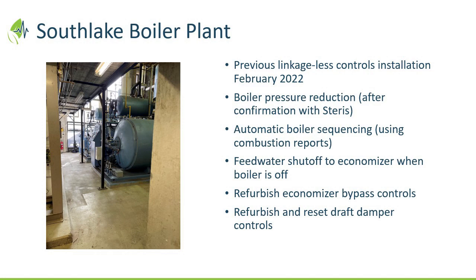My recommendation is absolutely bring in your service technicians even 4 times a year, right? We go through significant seasonal change, and that needs adjustment all the time. I think Enbridge at one point was even incentivizing what they call factory recommissioning. So essentially coming back in there, checking your gas and air, and if you don't have control over those inputs and outputs from a pressure perspective, it absolutely pays off. So I think quarterly, semi-annual for sure, is something everybody should be doing.